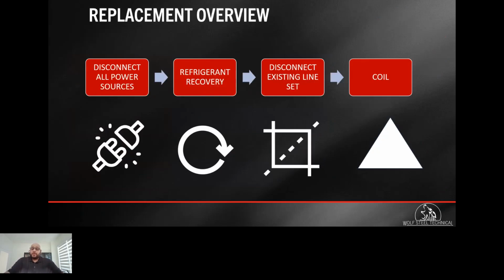So first and foremost, before taking anything apart, we do want to disconnect all the power sources to avoid any injury to the electrician. If existing AC equipment is present, you're going to want to recover the refrigerant. You should have your ozone depletion substance certification when handling these refrigerants. Once this is complete, disconnect your lines and your line set and remove your coil.